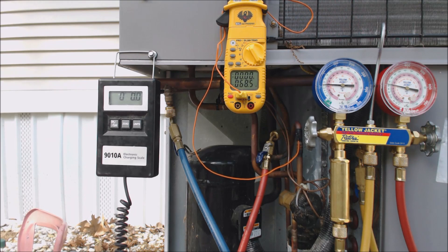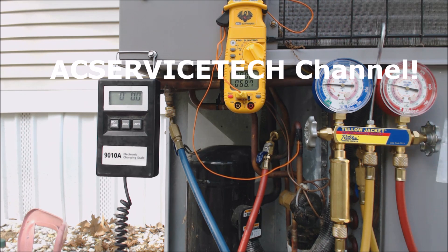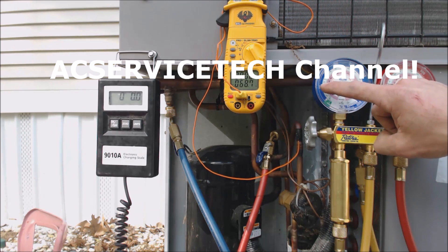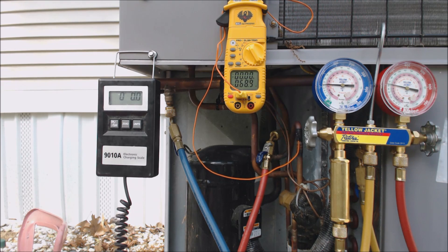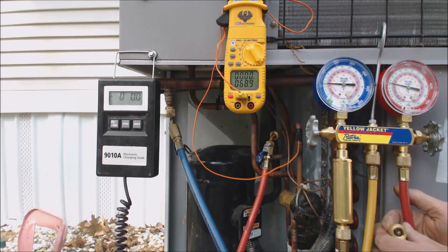Hey guys, this is the ACServiceTech. Today we're looking at charging a 410A package unit that's low on refrigerant charge. If you look at this gauge right here, we're at about 60 psi, which means our saturated temperature inside the evaporator coil is about 8 degrees, so we're going to go ahead and attach our 410A bottle.